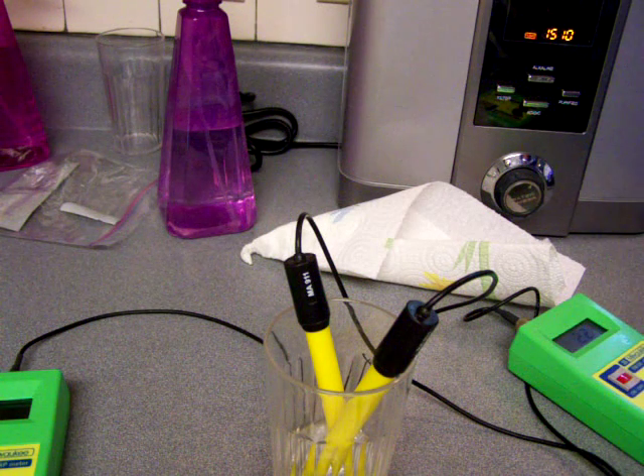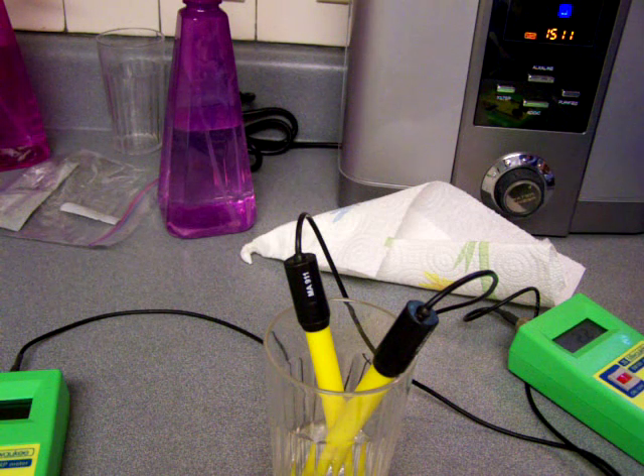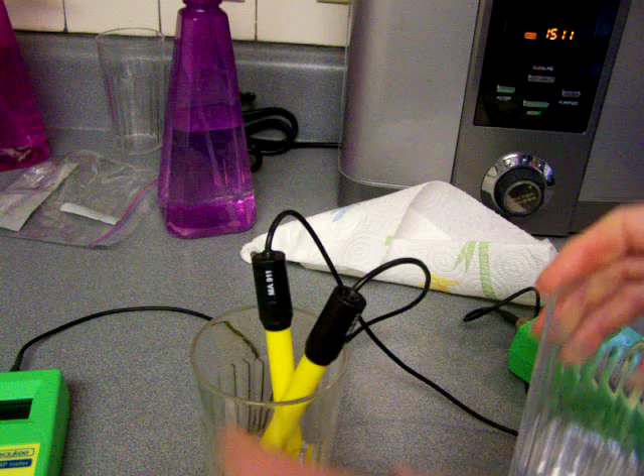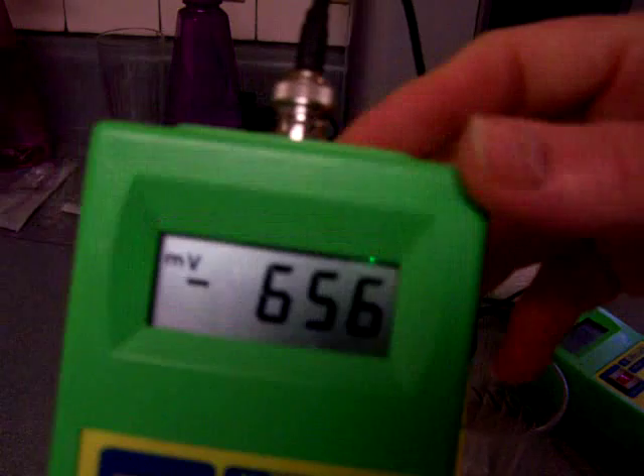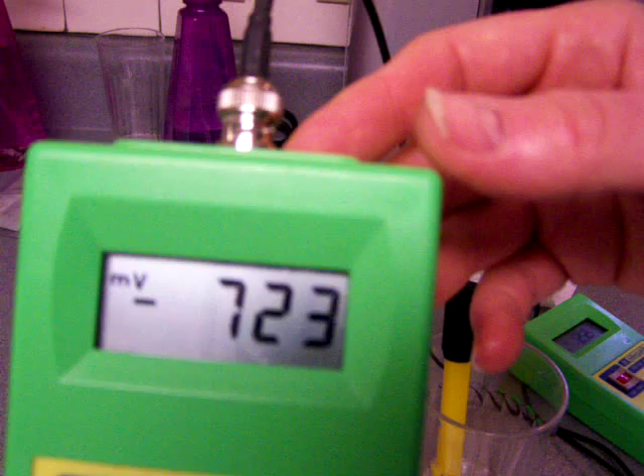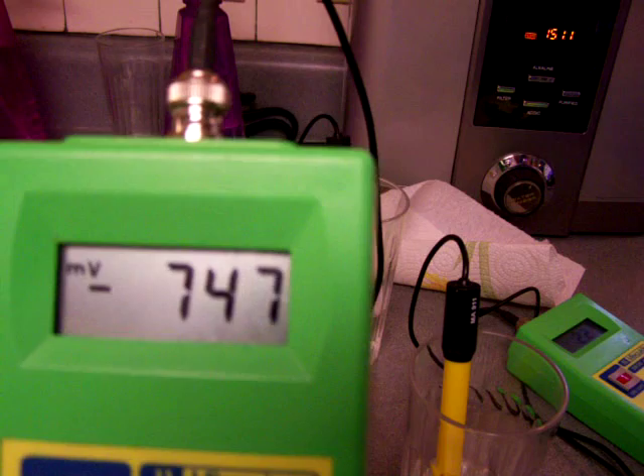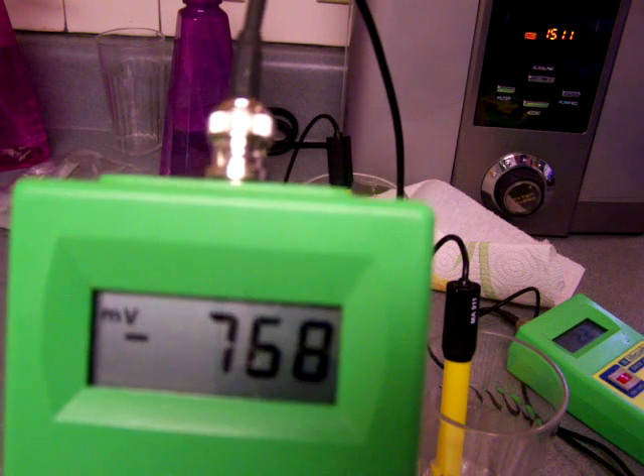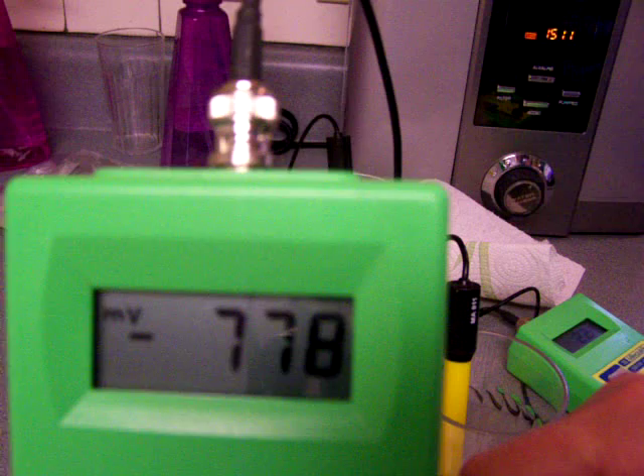I'll get some more ionized water to test it. If it comes up closer to the negative 700-ish, which it should be, once it gets up to around negative 700 or a little better, I'll be satisfied because that's what I'm used to and that's what I know the Athena will give me. Let's see what it's giving me. Well, actually that is getting better—negative 600, negative 700 something. I'm not really used to cleaning it so quickly. Usually I have to do what I just demonstrated twice at least to get it clean. This particular time it had—it was clean to begin with.